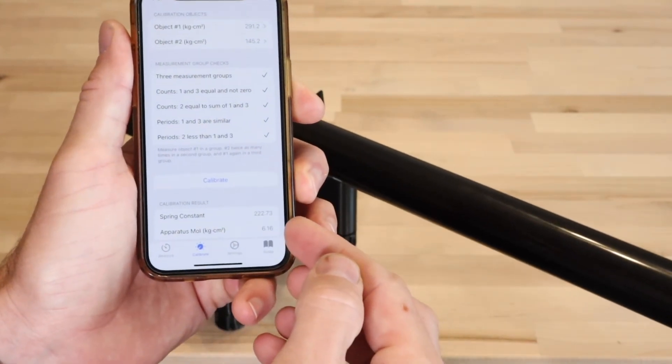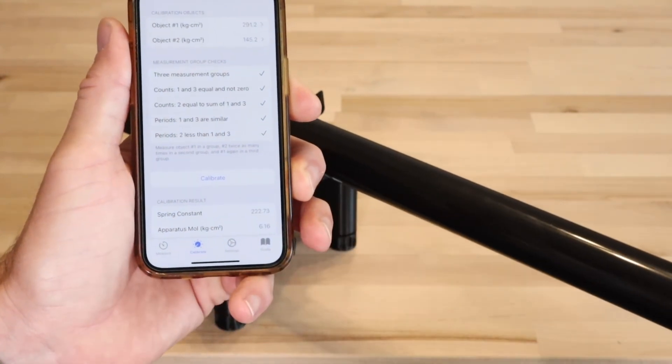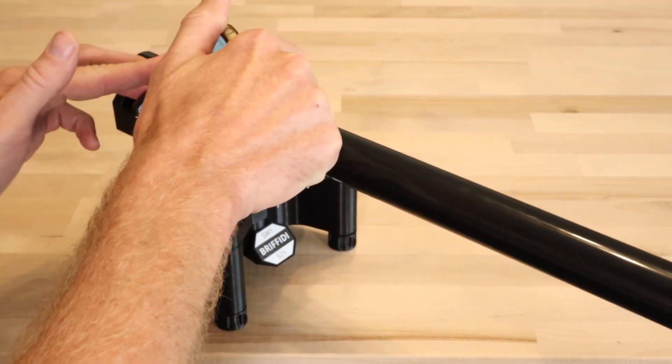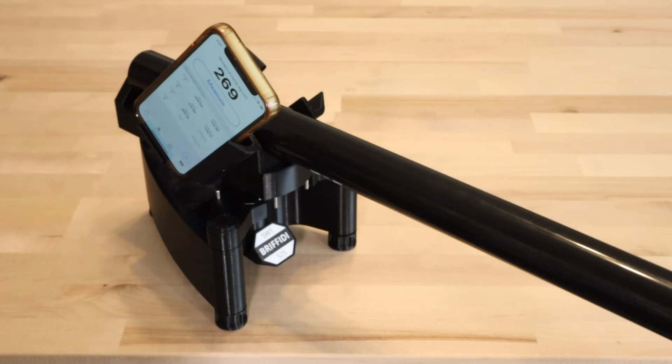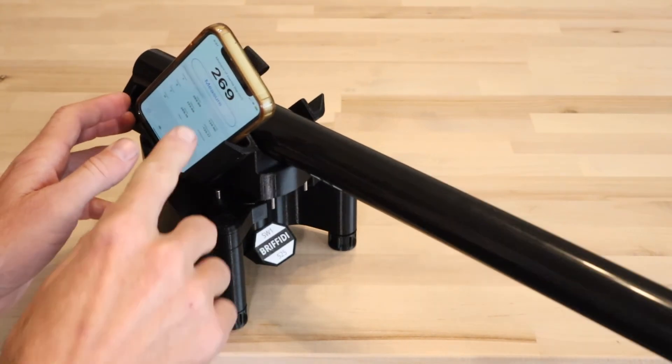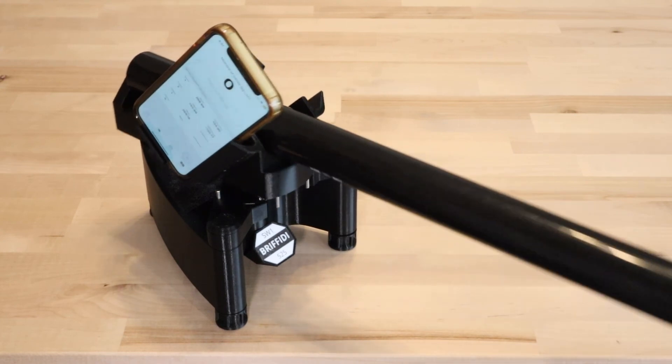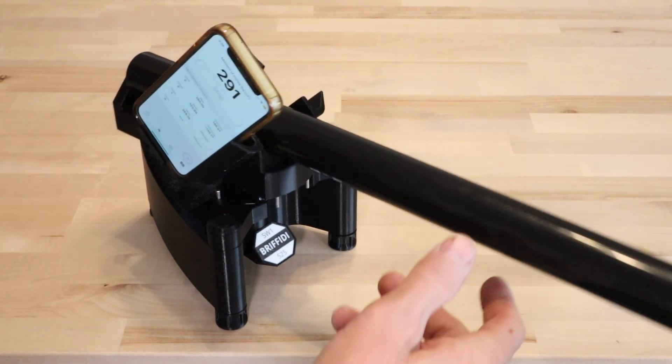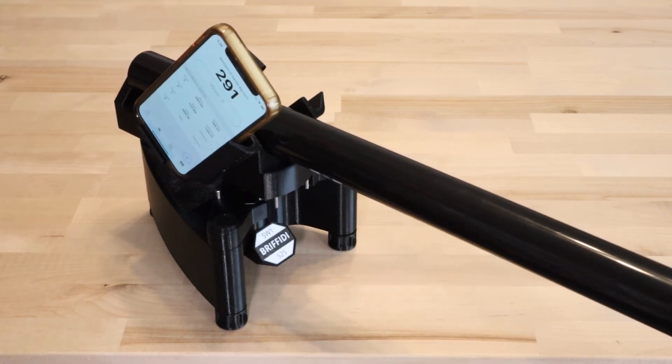The calibration result at the bottom of the screen will update. You should now be able to measure the calibration rod and match the values printed on the label. It was measuring 269, but now measures 291, which matches.